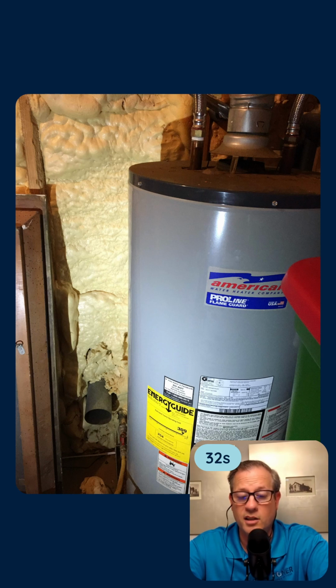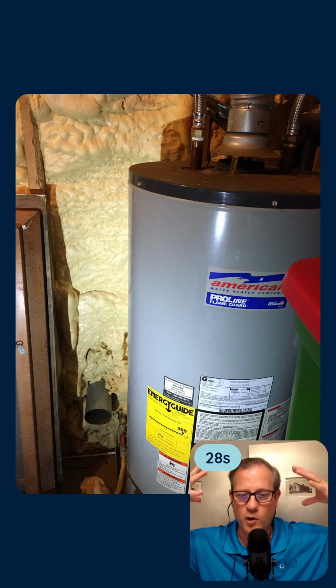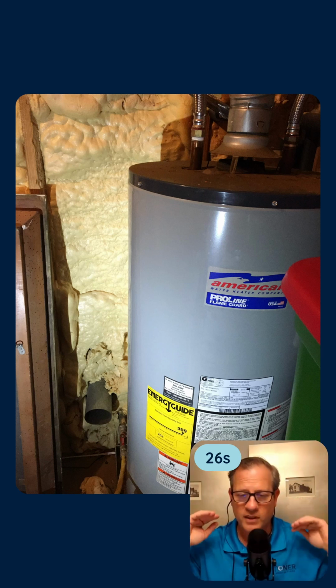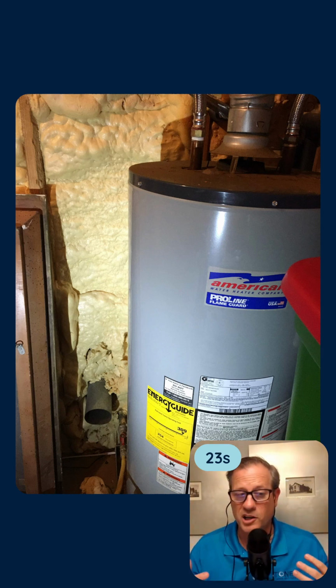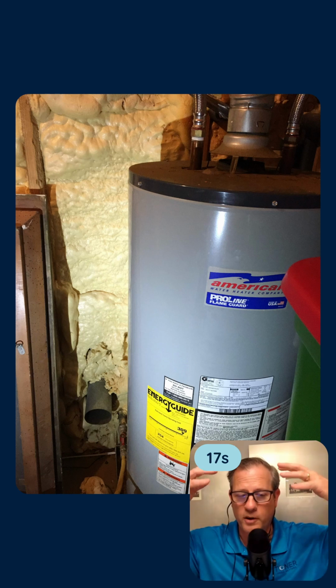So they thought they could bring in some makeup air for it. That's the vent down below. But you see how the foam goes from real fluffy to real thin? They were also concerned about combustion. So in order to get the foam away from it, they went with a more high density foam, a closed cell foam. They went open to closed cell.